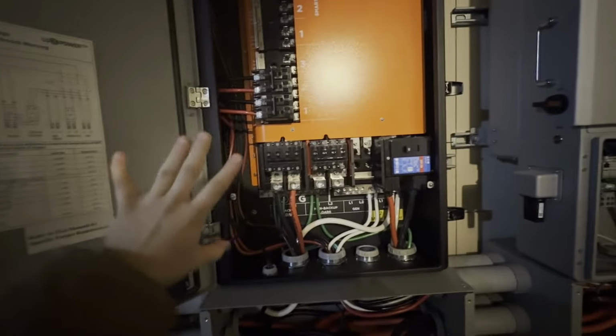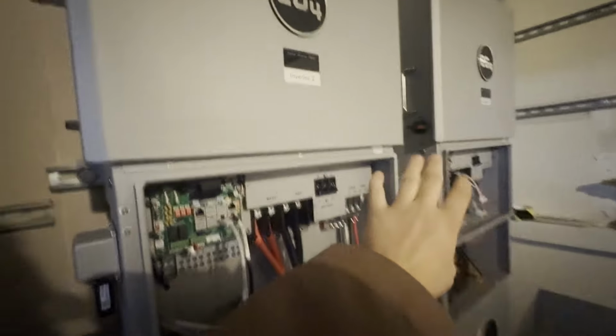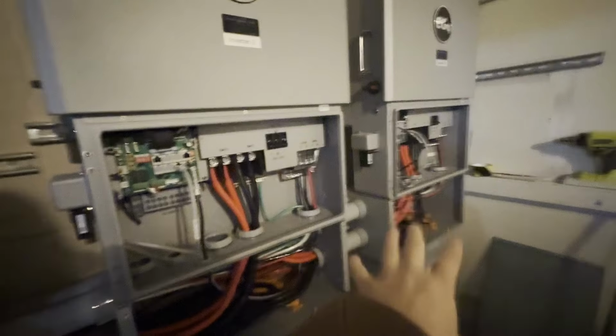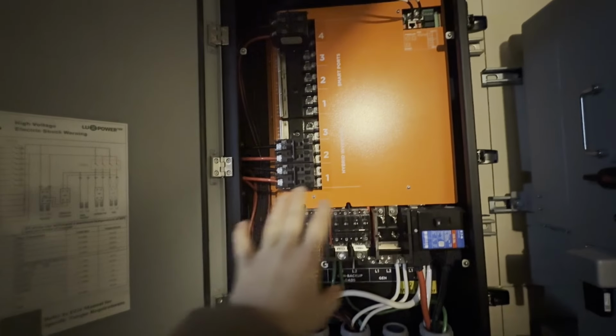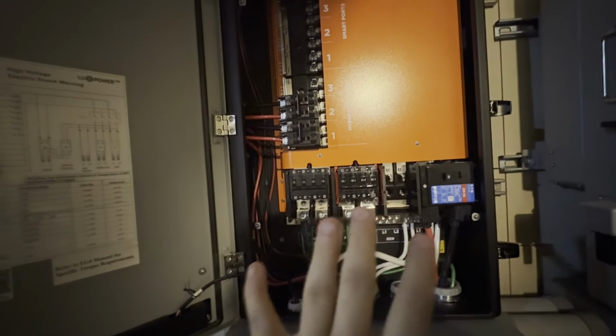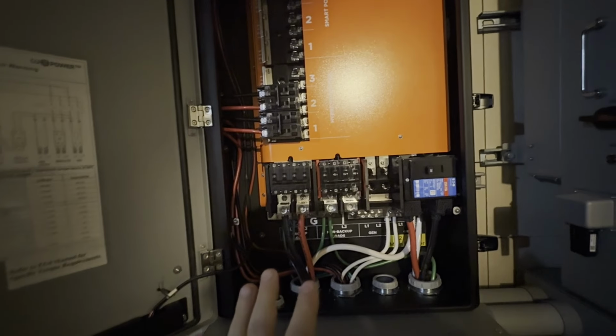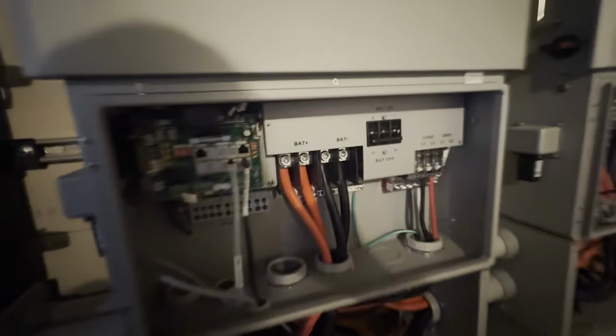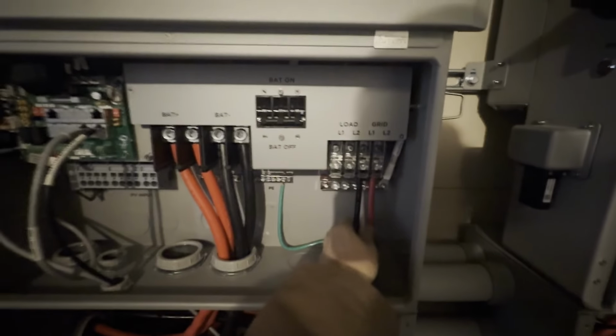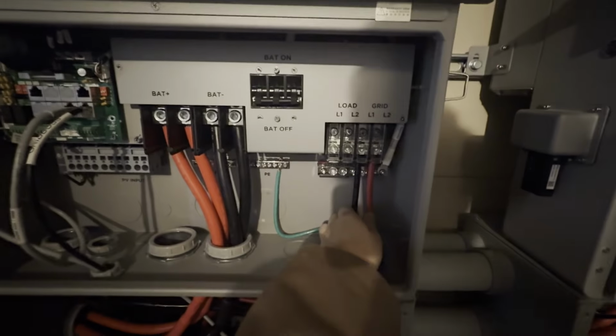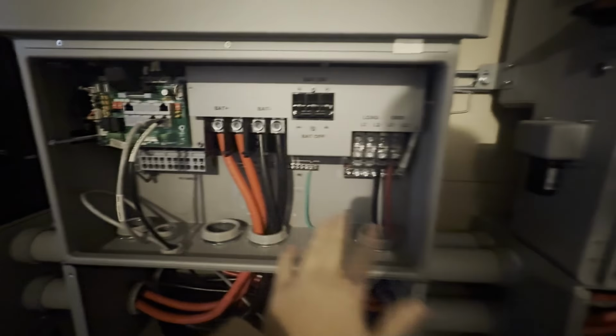This thing is great. This basically simplifies all of the electrical setup, because normally with an inverter setup, the power comes in from the grid to the inverter and then out from the inverter to your loads, which starts getting a little bit more complicated when you've got multiple inverters. But in this case, everything's handled by this, and there's a lot less wiring needed. So in the case of the inverters, the only real wiring needed is the connection to the grid boss, and then the connection to the batteries. I don't have to do a connection from the grid and then to the loads and all that.